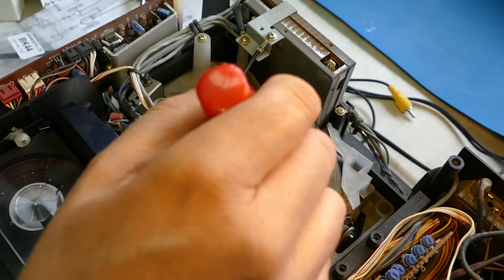If you were to change the heads on one of these machines, it's not quite the easiest job in the world. You have to remove a lot of these screws and take the top static drum off, and then the head disc is inside. You've got to desolder four wires, and make sure you remember which ones go where.